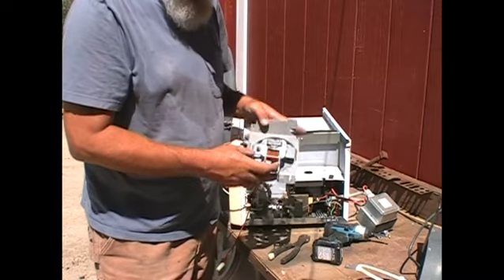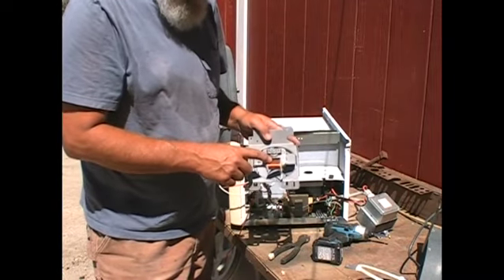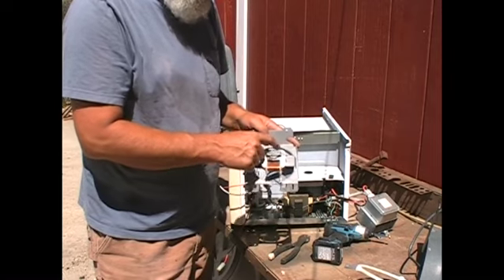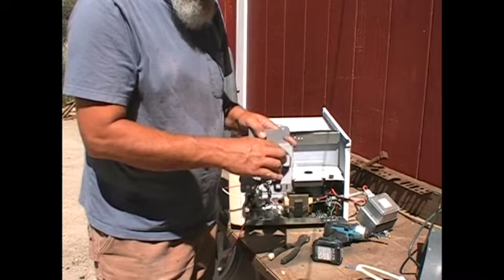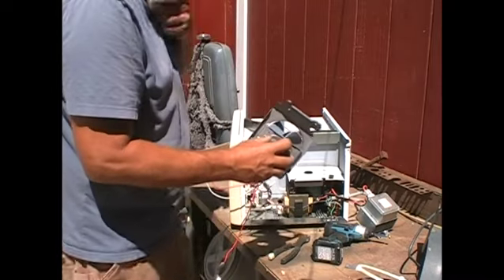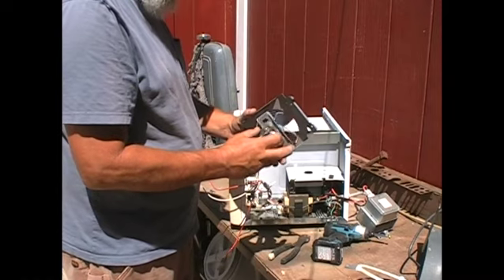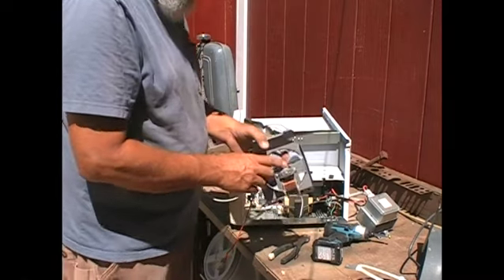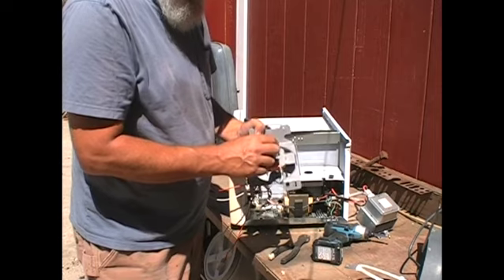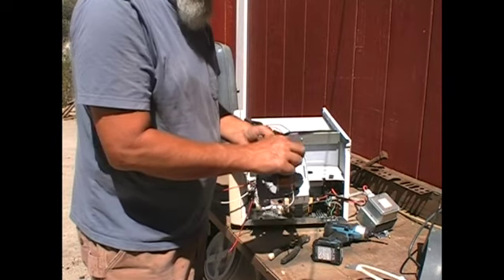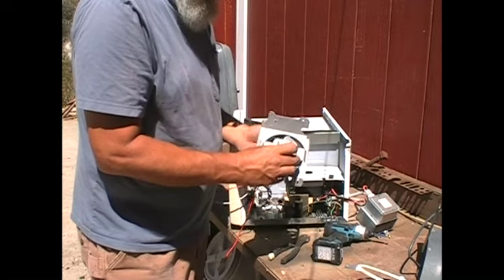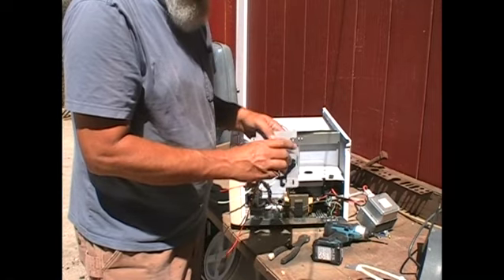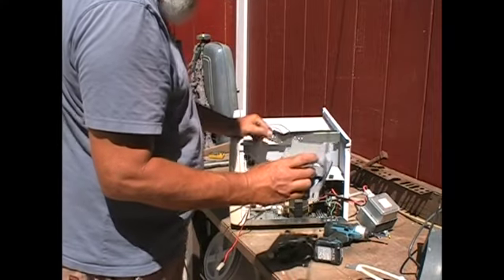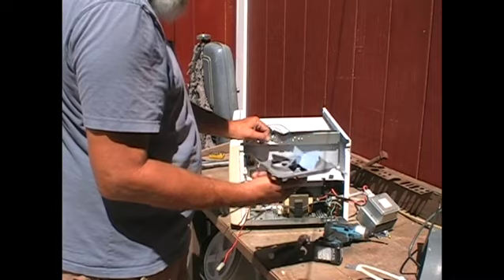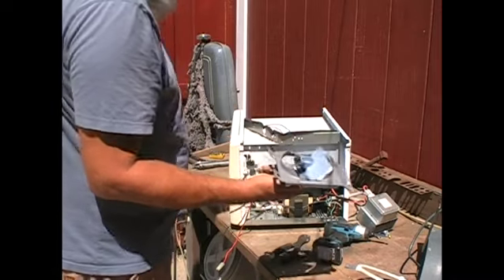This is a shaded pole motor. It uses induction through this coil to set up a magnetic field through this iron core. That magnetic field, oscillating back and forth, induces a back EMF into this rotor, which causes the fan to spin. This little copper loop here causes a slight retardation of the magnetic phase on this side to give it a difference, so it doesn't just sit here and hum back and forth, it will actually spin. This is a very low current motor, low starting torque, really not that efficient, but it does the job. You just want to move air.